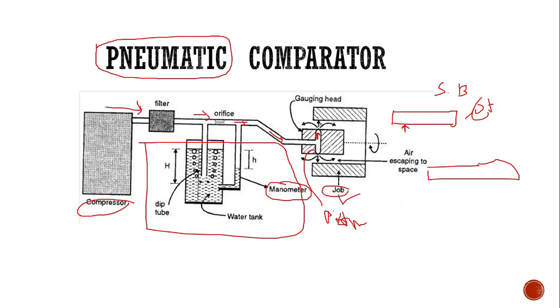If the value of back pressure is more, what does it mean? This hole is smaller than required, so I have to again make a cut with the help of a drill so that it can be increased. Again I have to do the same thing: move the hole over this component or piston, and measure the back pressure again.